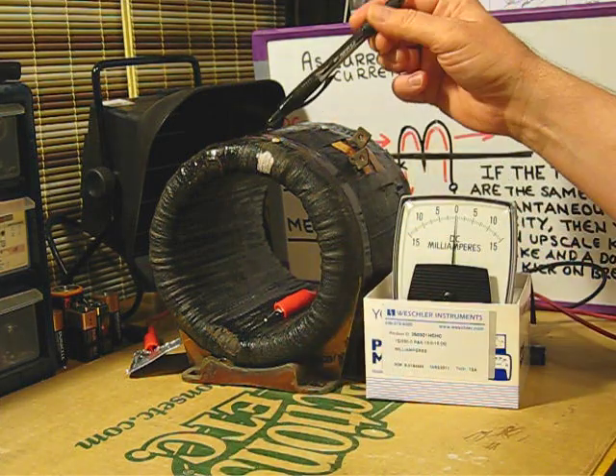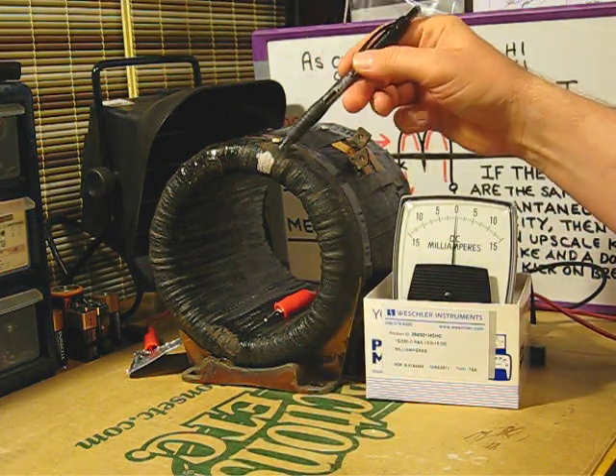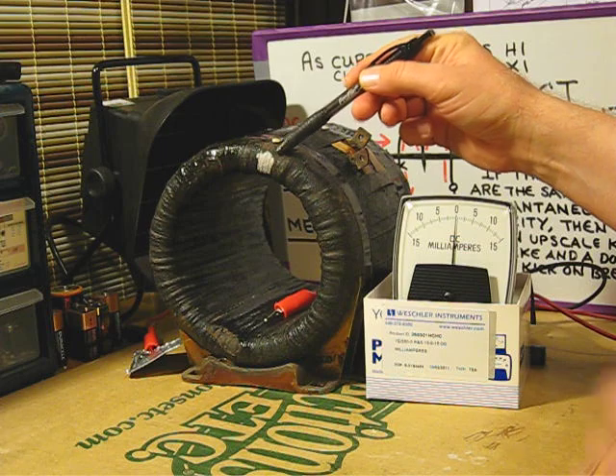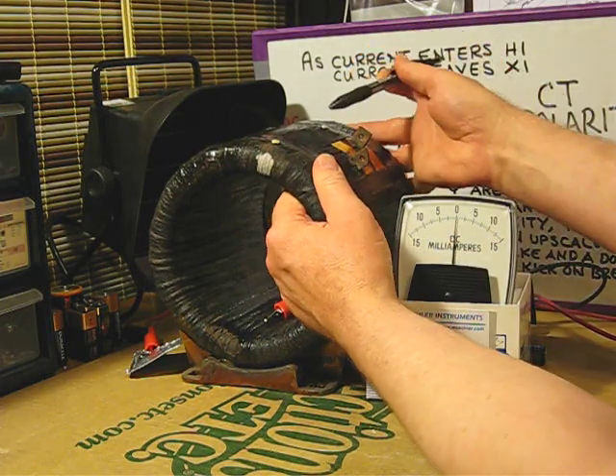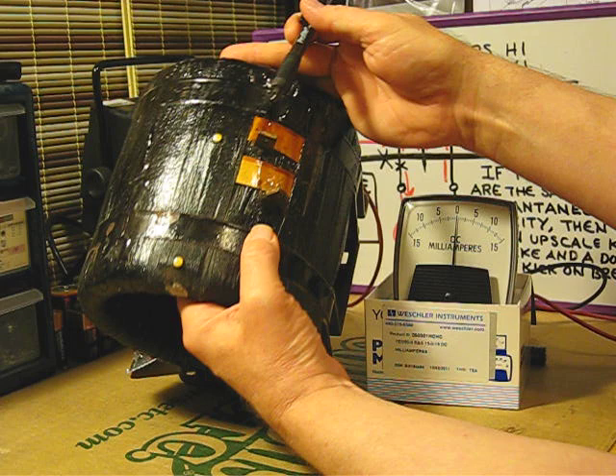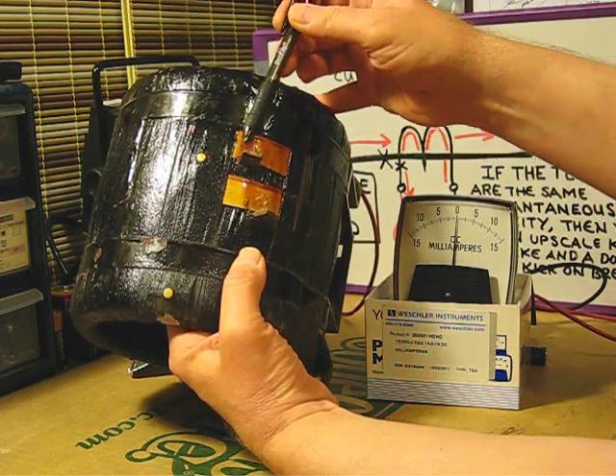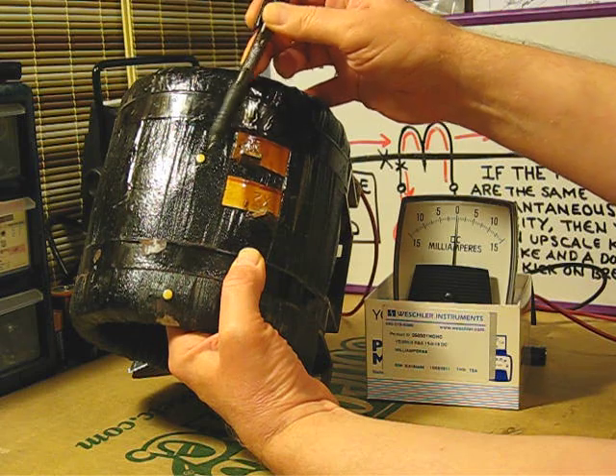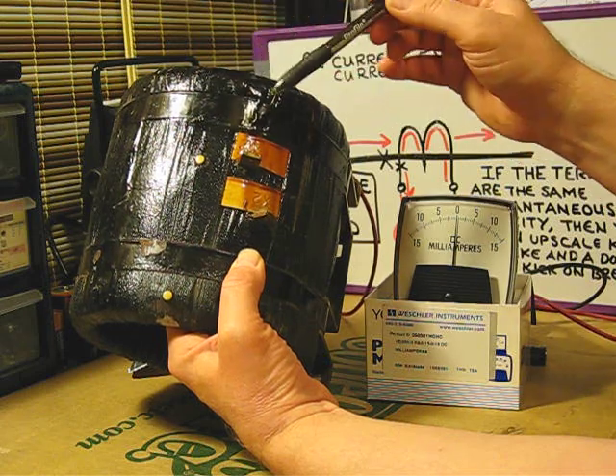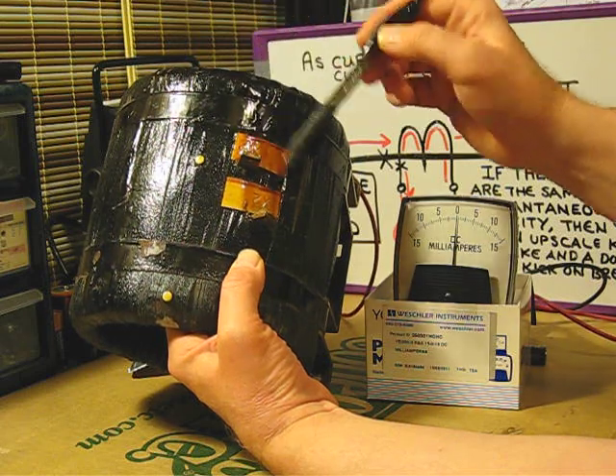Here, the H1 side is designated with white paint and also a white dot or white raised bump. The secondary terminal X1 is designated as the terminal closest to this white bump, and it also has tags that read X1 and X2.